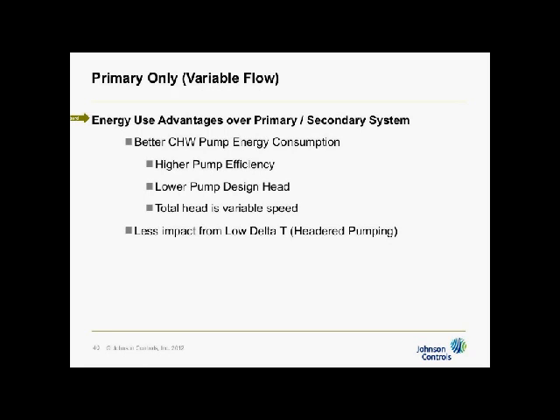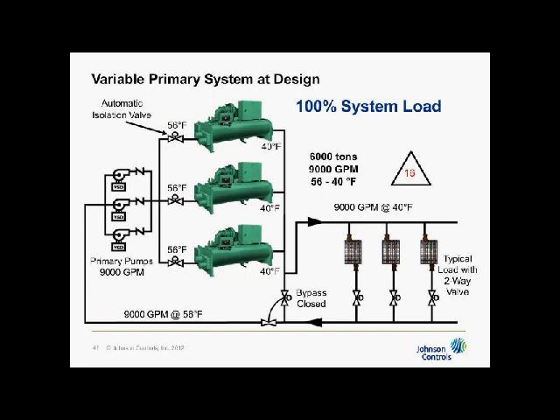Now we have an additional one. We have less impact from low delta T because we can, with headered pumping, mitigate low delta T. We can't solve it. You've got to do that at the loads, but we can mitigate it. Let's look at the same view we had of the primary secondary, but now VPF. Now we have our headered pumps over here.